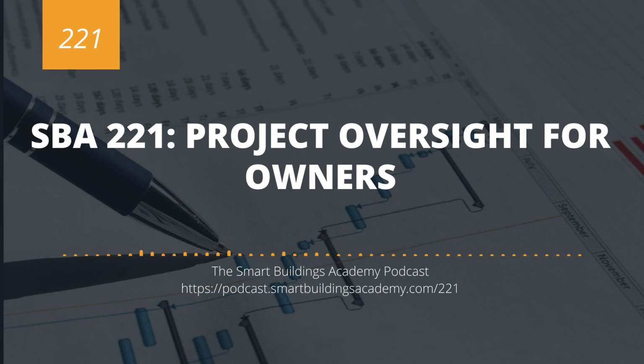Now, to that point, you have to make a decision at this point. Do I want to have a performance or a prescriptive spec? A performance spec says, this is the outcome I want to achieve, and it leaves it more open-ended. There is the possibility for value engineering. There is the possibility for going over cost. There's the possibility for implementing something that you don't necessarily want, but there's also the possibility that you get everything you want and you get it at a lower price. So performance specs can be good from that perspective, and they can expose you to contractors who may not have qualified if you had a more prescriptive spec.